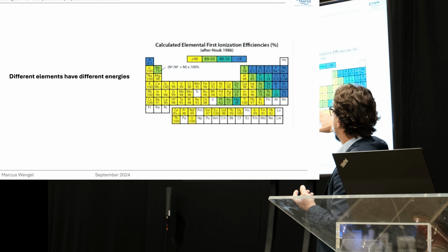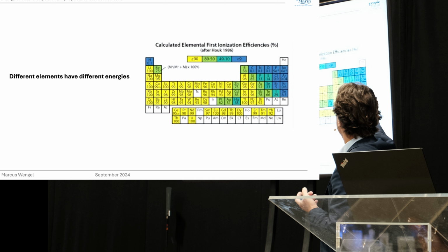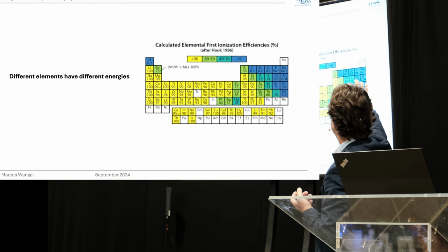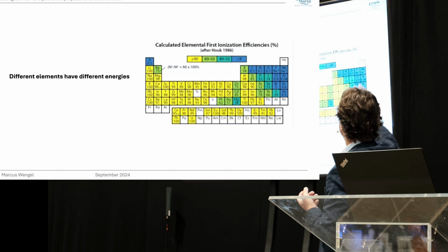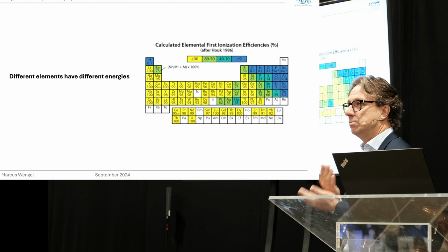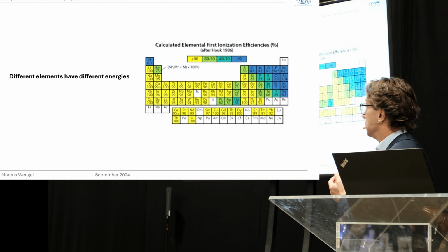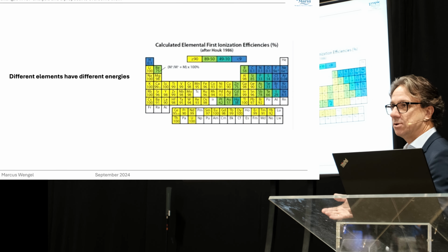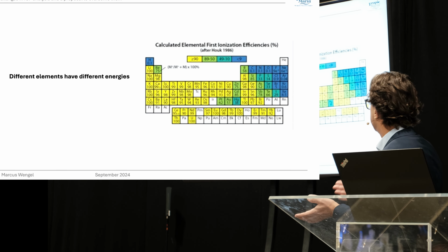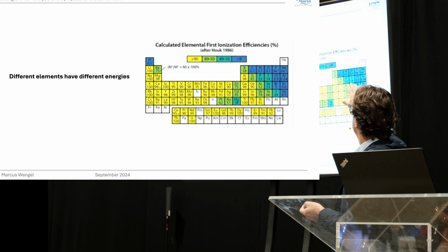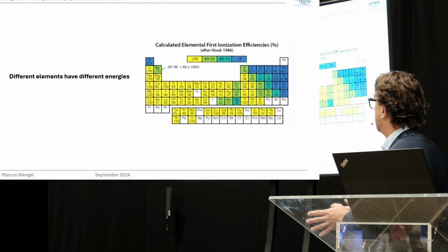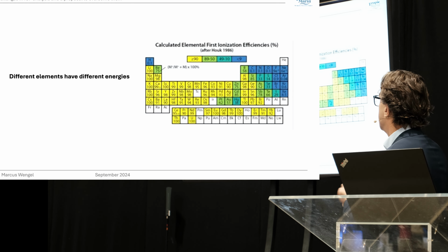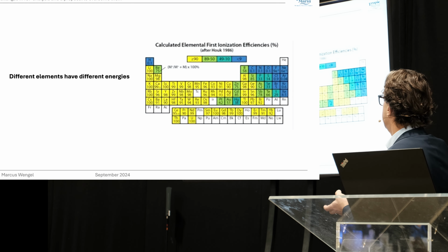And if we watch the periodic system, on this right part, only 10% or a little bit higher of these elements are able to be measured in the system. So 90% we are not able to measure in the whole matrix. So things like chlorine, bromide, it's not easy to measure in ICP analysis because their energies are not high enough to get ionized there.